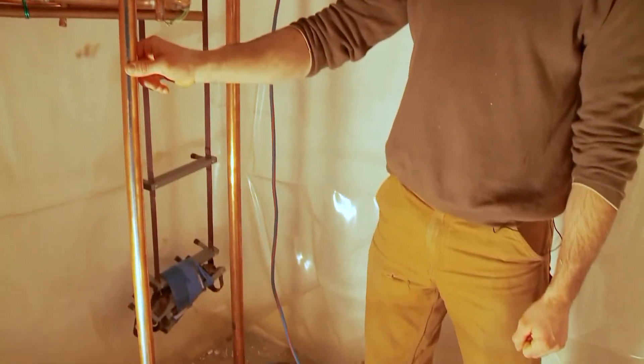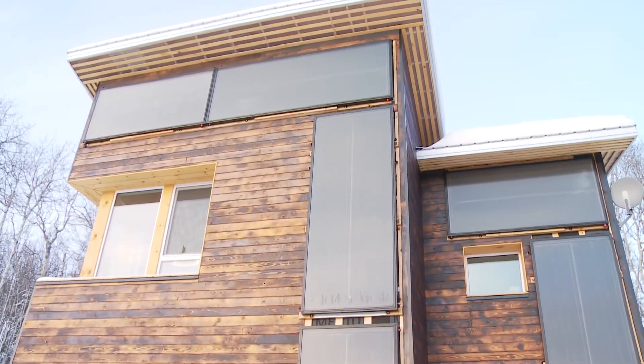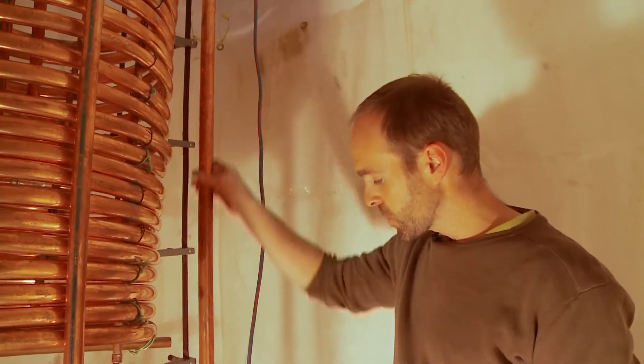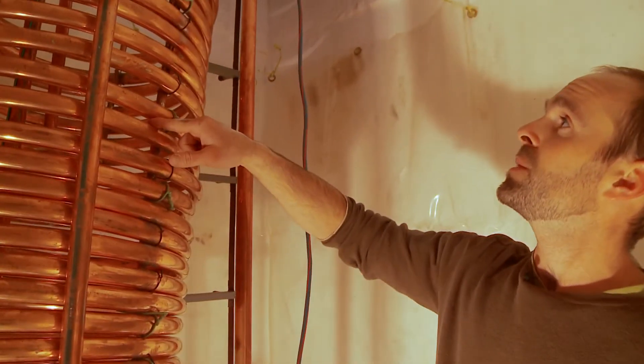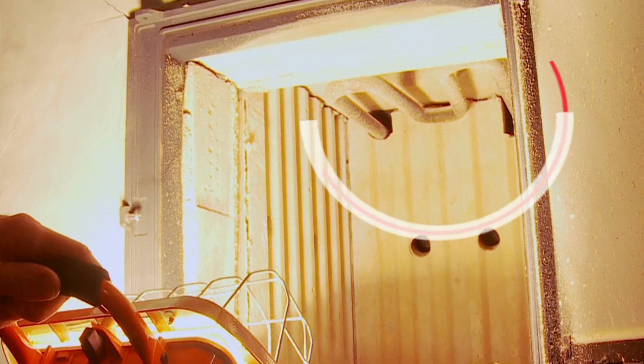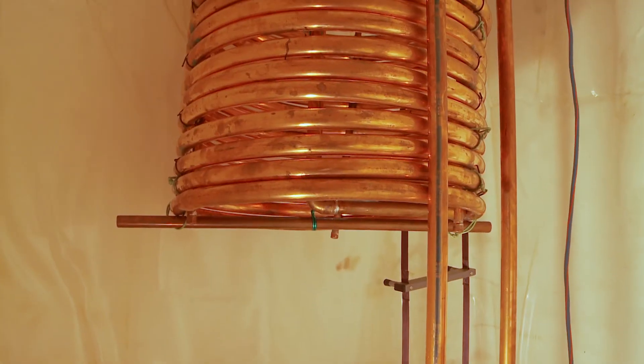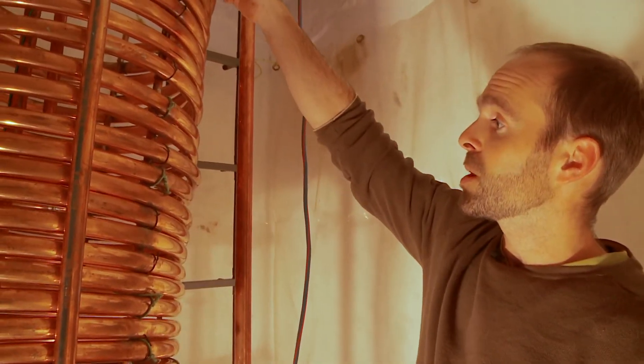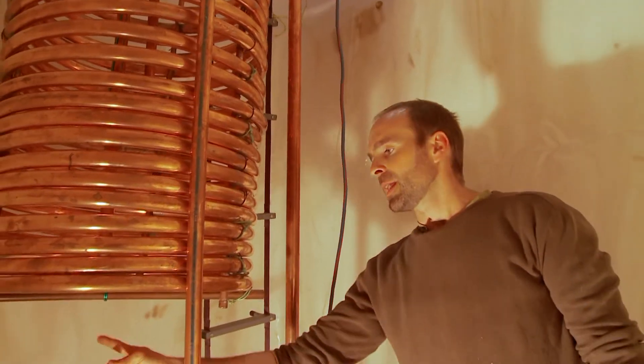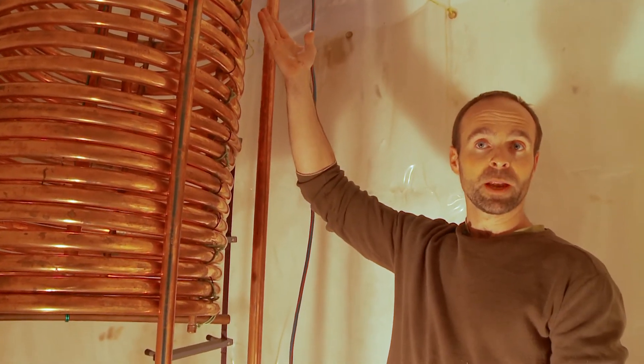This pipe sucks water from the tank, sends it up into the solar thermal collection system where it gets heated, and returns to the tank through a pipe into the solar stratifier. There's another pipe here that goes up to a coil inside the firebox of the masonry heater, and it too comes back through this pipe into the stratifier. This is my domestic hot water heater — the tank is full of hot water, and we pump cold domestic water into this coil, where it warms up so that by the time it leaves, it's at a temperature I can use for a shower.